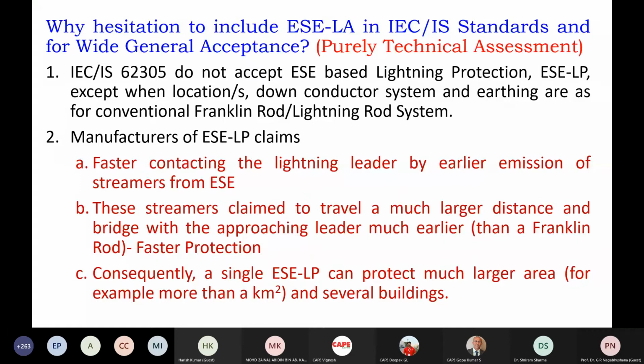IEC 62305 does not accept ESE-based lightning protection except when the locations, down conductor systems, and earthings are strictly as per conventional Franklin rod lightning rod systems. The number, the down conductors, the earthing system must be the same as for Franklin rods. Only then it is acceptable. That is a very good statement.